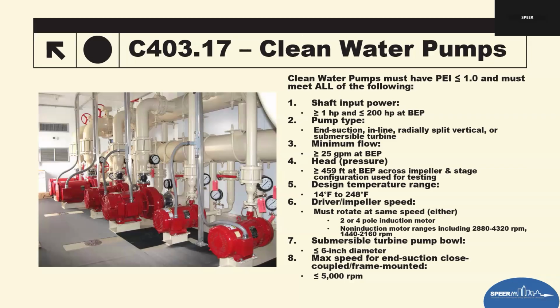Field inspection tip: ensure the installed pump matches what has been approved through the submittal. Verify the motor nameplate speed matches the pump speed, and then confirm the pump and motor are listed with compliant PEI values.